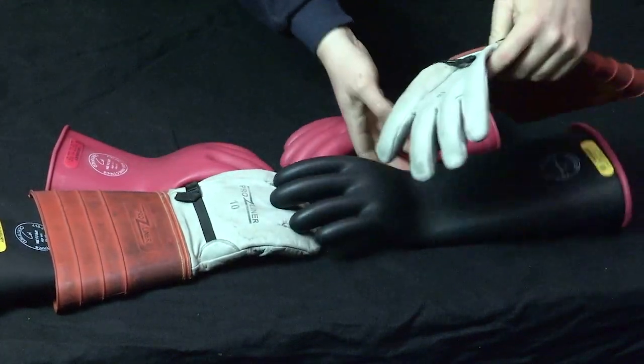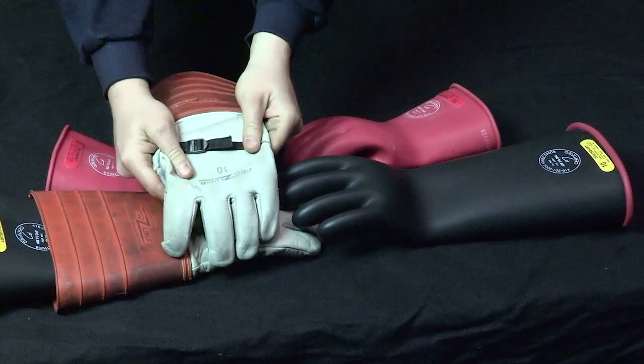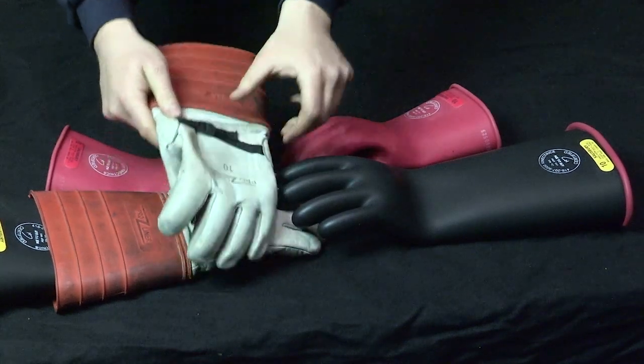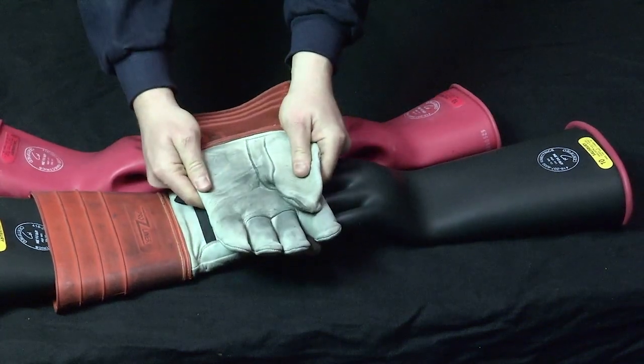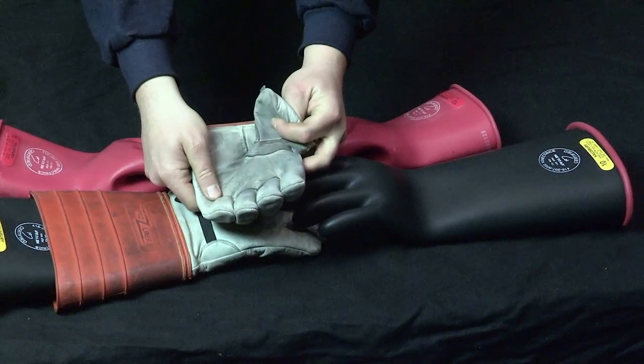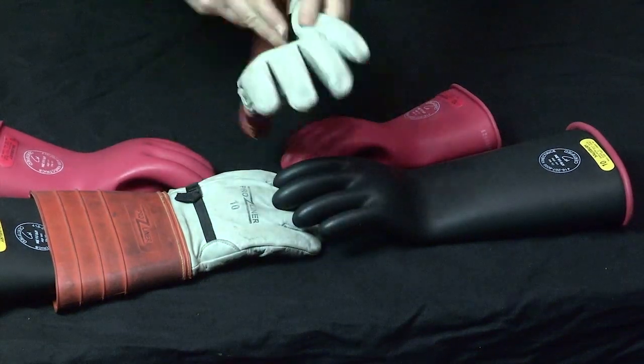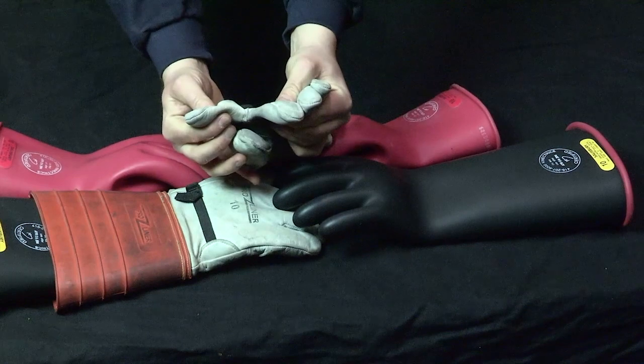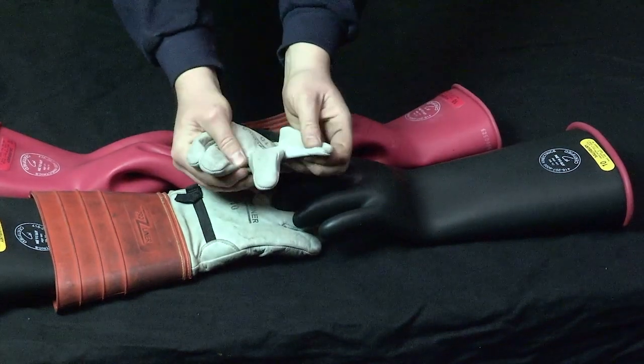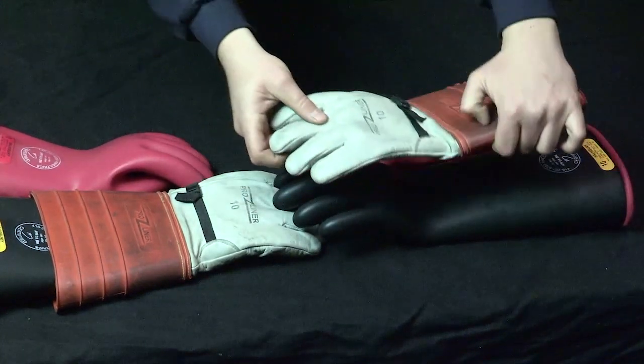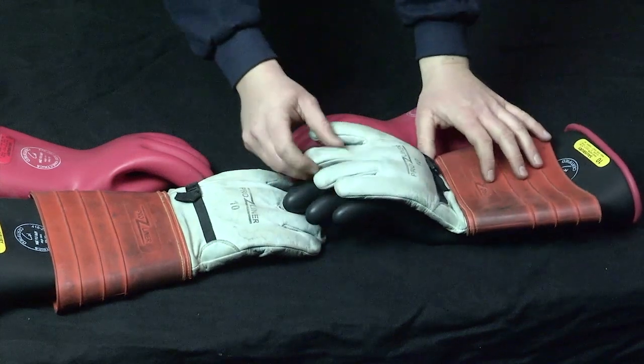Check the glove cover for any wood or metal splinters that could puncture the rubber gloves. If the covers are oil or penetrox soaked or worn through in spots, they should be replaced. A cut through the leather or synthetic part of a glove cover should be investigated to see if any damage has been transferred to the rubber glove inside the cover.